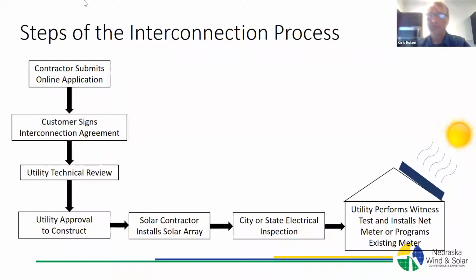Once the electrical inspection is completed, it's important for the inspector to send proof of that successful inspection to the utility, because the utility needs that documentation to perform the witness test. That's the final step, where a utility representative goes to the customer site to make sure what was installed matches what was approved.